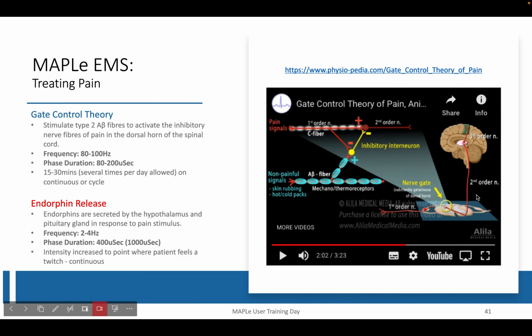And again, that phase duration, if it feels too sharp for the patient, then bring the phase duration down. This could be completed for between 15 to 30 minutes. It could be several times a day, but obviously in a clinic setting, that is going to be difficult. But it should be on a continuous or cycle. So you can have it with contractions or without contractions. But in my practice, I tend to use continuous more so in the early stages, so that the patient can get used to that sensation and the effects of the treatment.